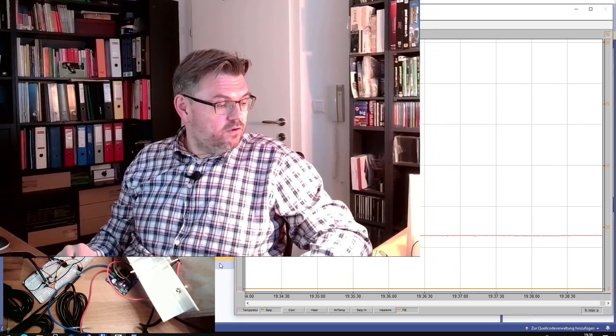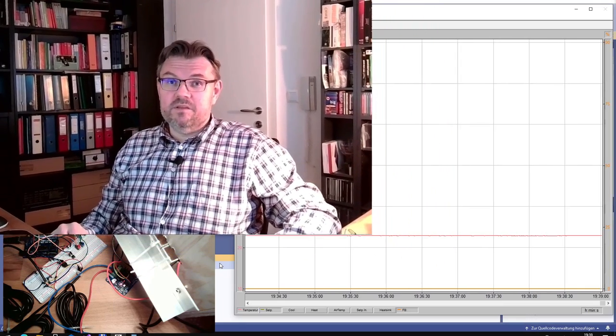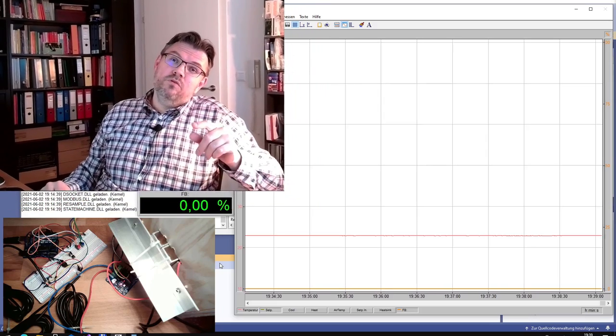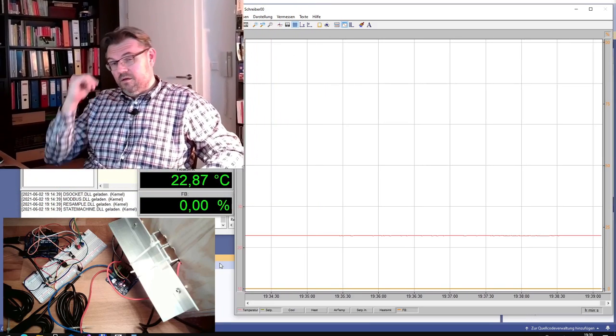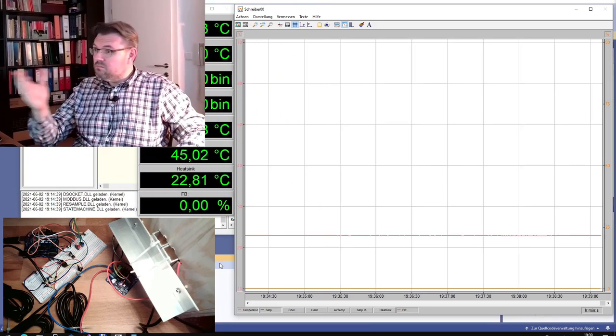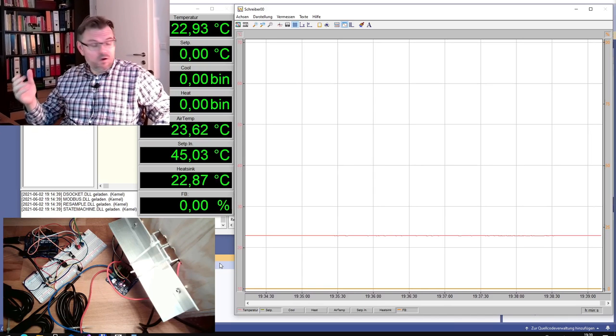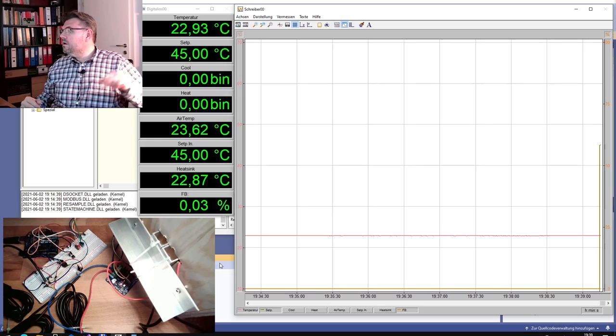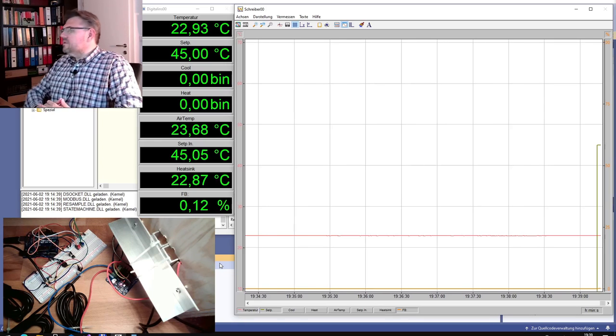Okay, now I changed TI by factor 10. I changed the integrational time by factor 10. If we're talking about KI, I would reduce it by a factor 10. Okay? So let's see how this is working now. I will again trigger the set point, and see what is happening.